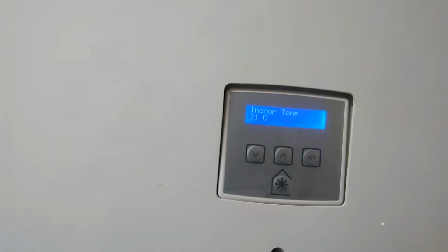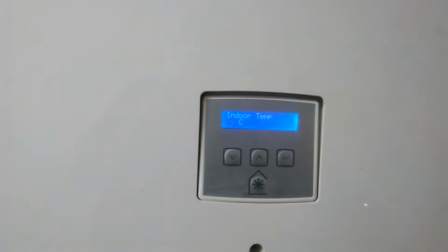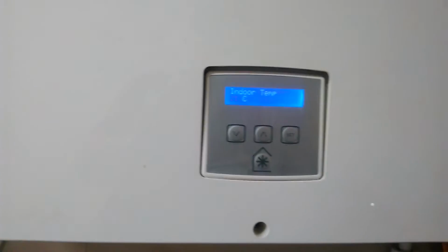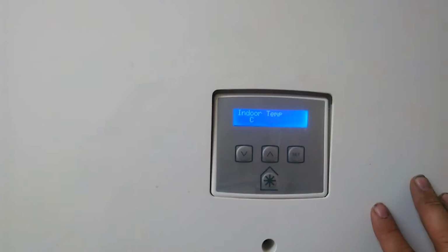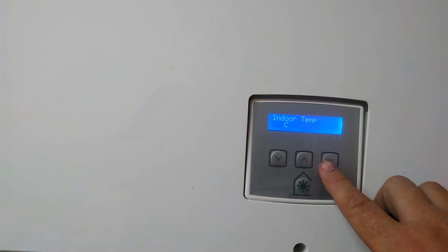So the internal temperature is set to the same as the boiler. Sometimes it's good to increase it 1 degree above your desired boiler temperature. Then that will compensate for any inefficiency in the MVHR system. So internal temperature, the summer bypass will kick in if we start to exceed 21 degrees C. Okay?